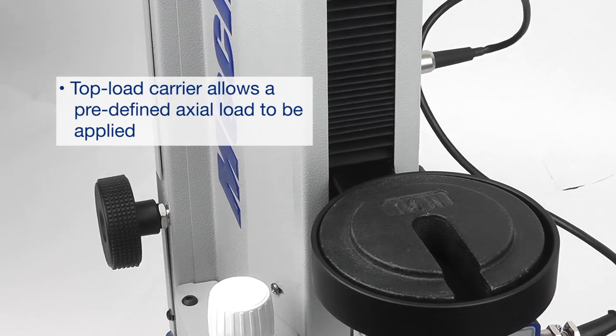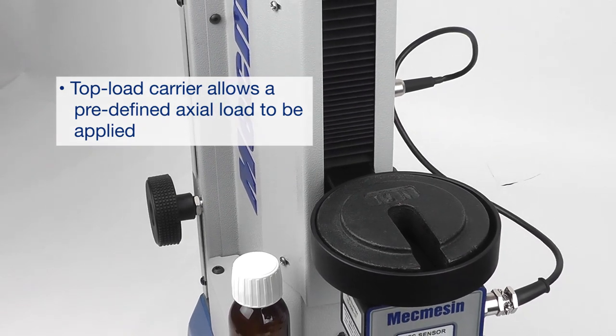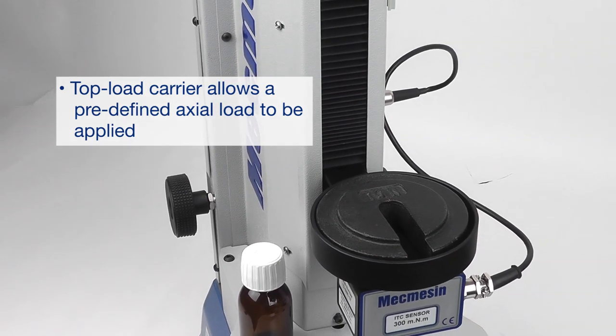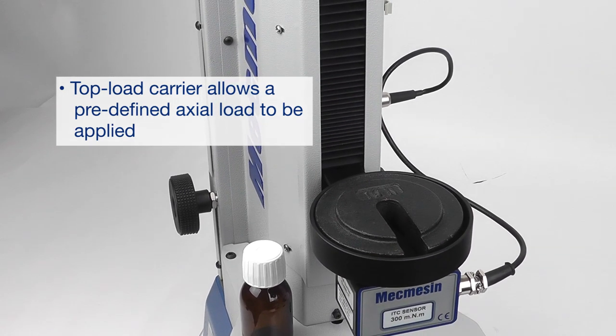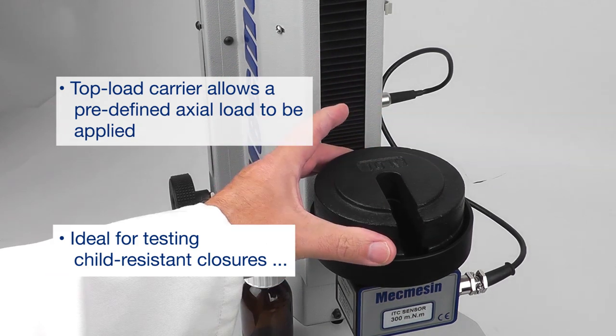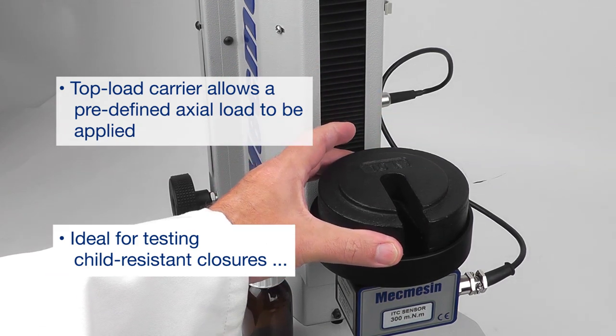The same counterbalance system can also be used to apply constant downforce, which is needed when testing child-resistant closures or Luer-Lock fittings on syringes or other medical devices.